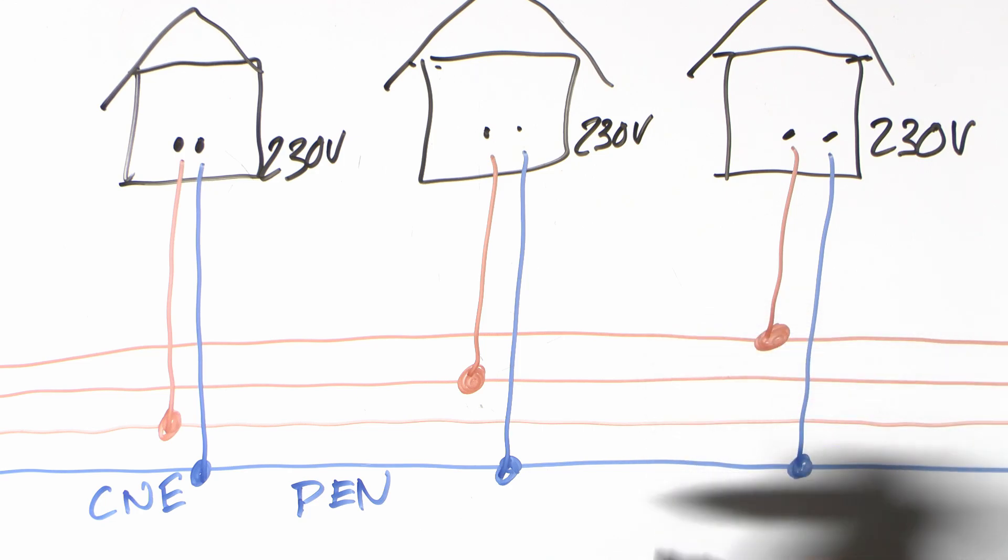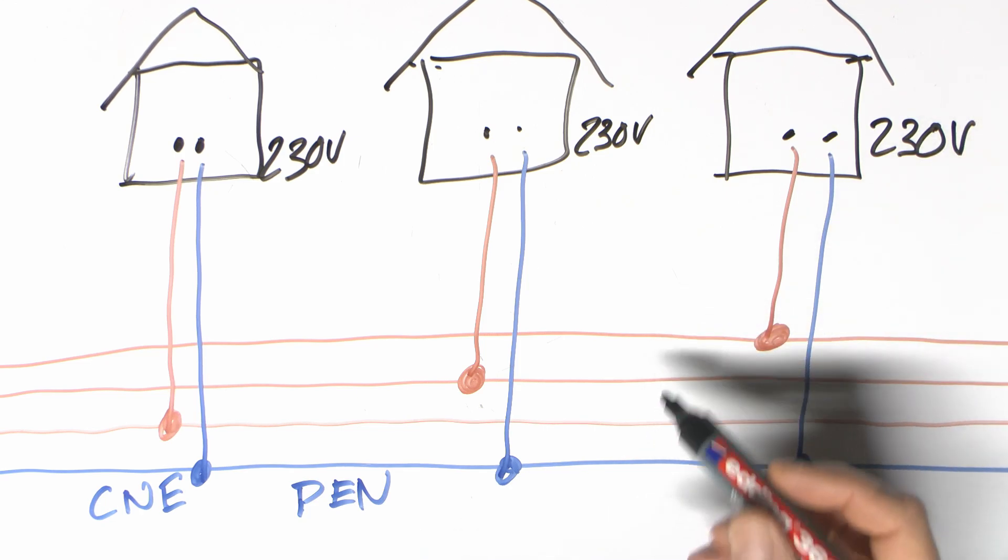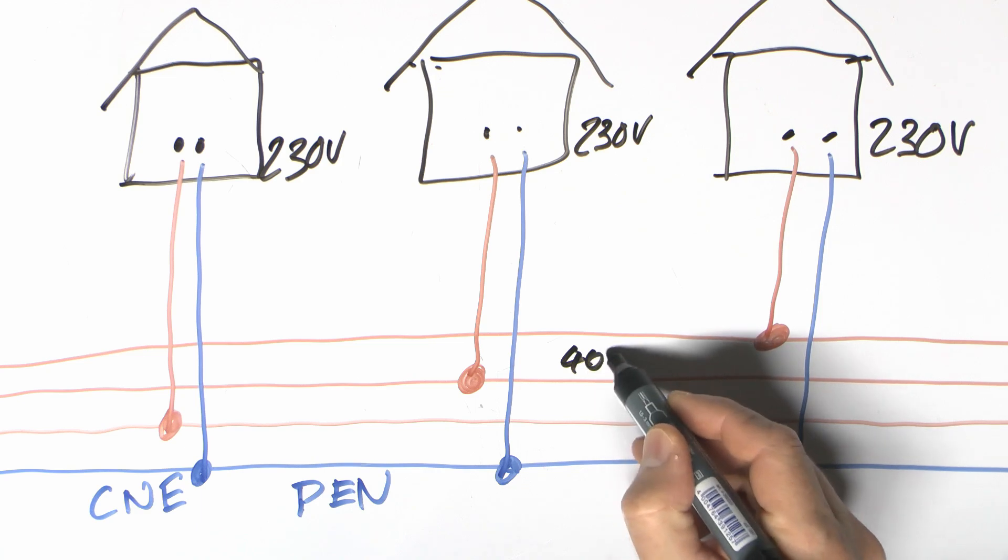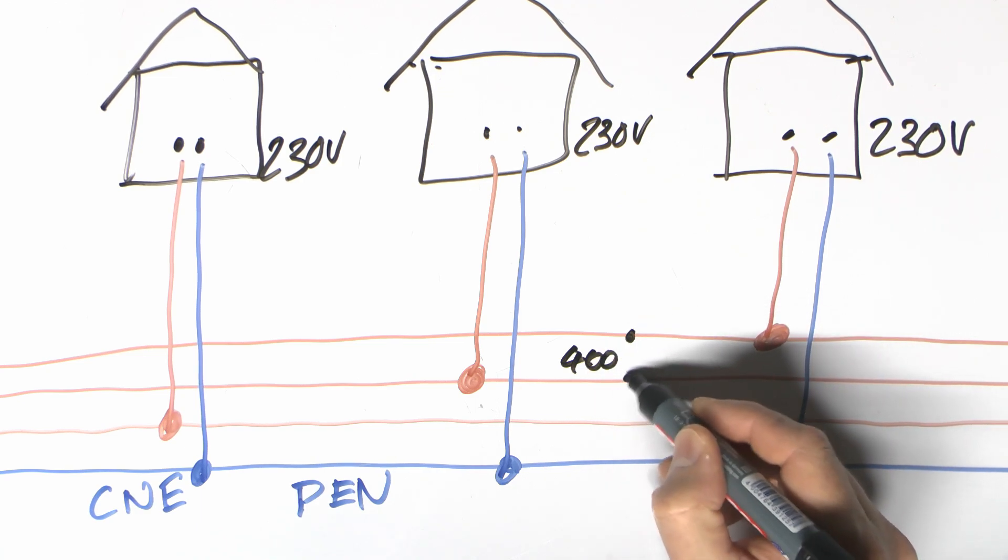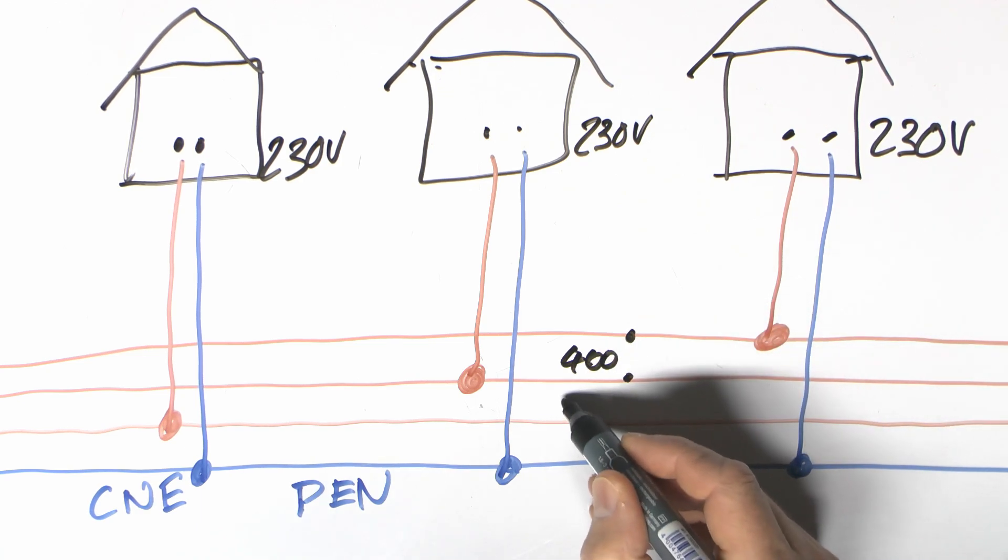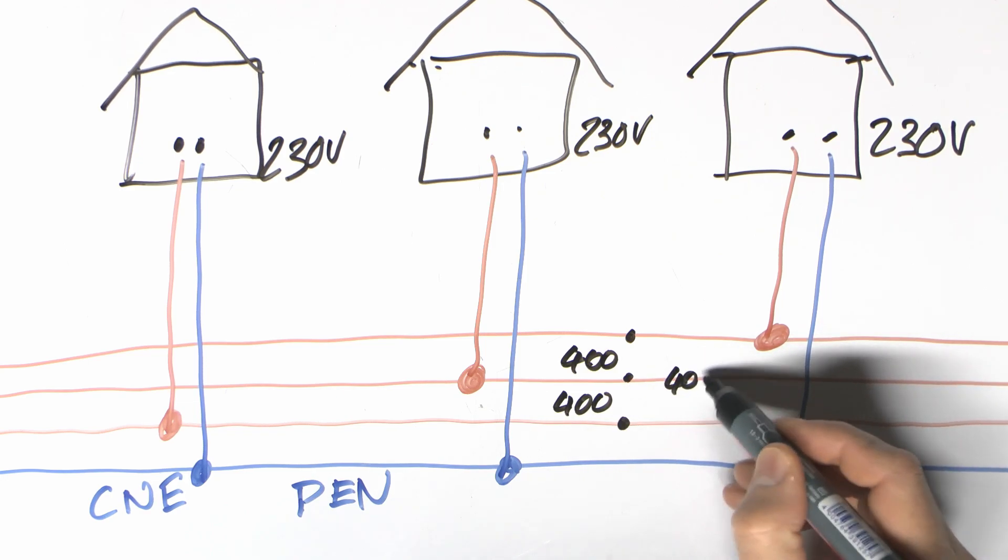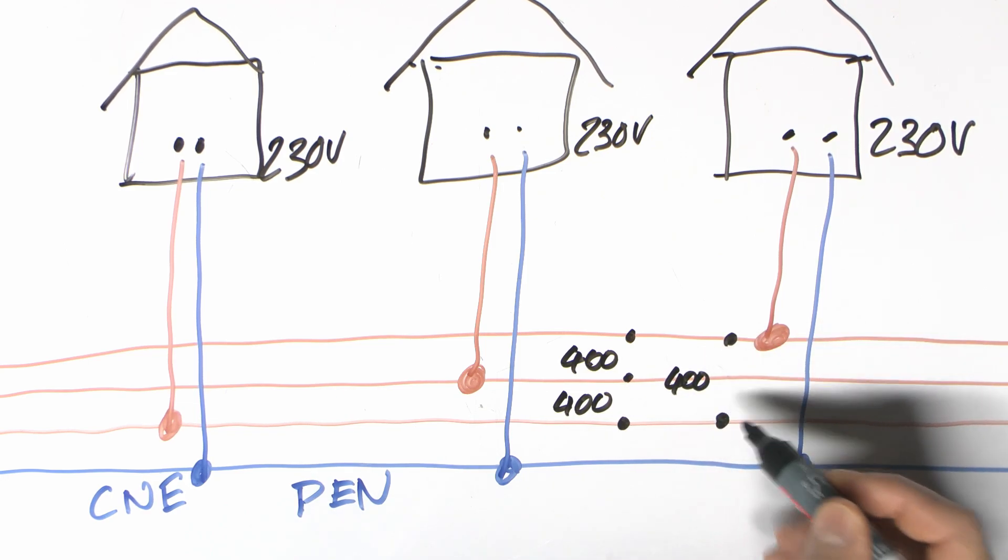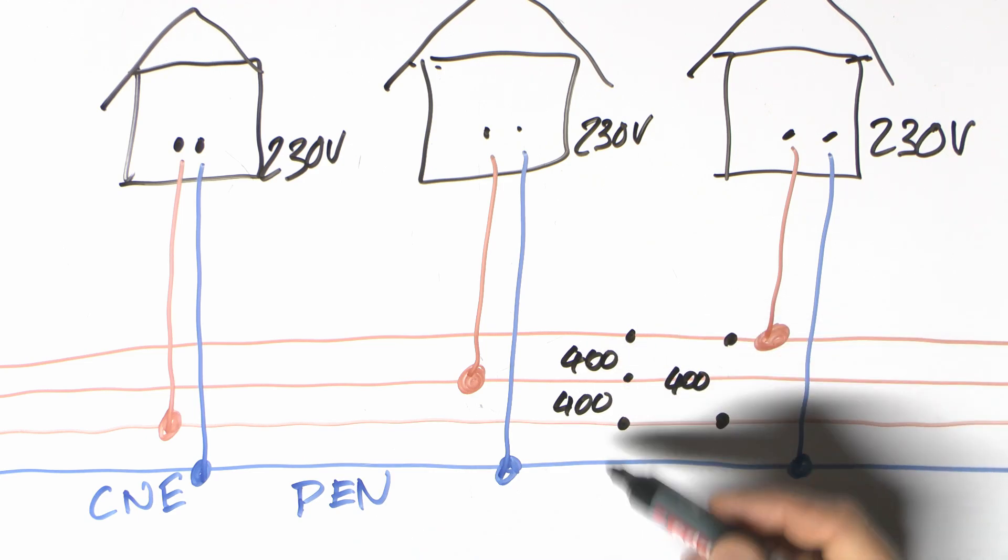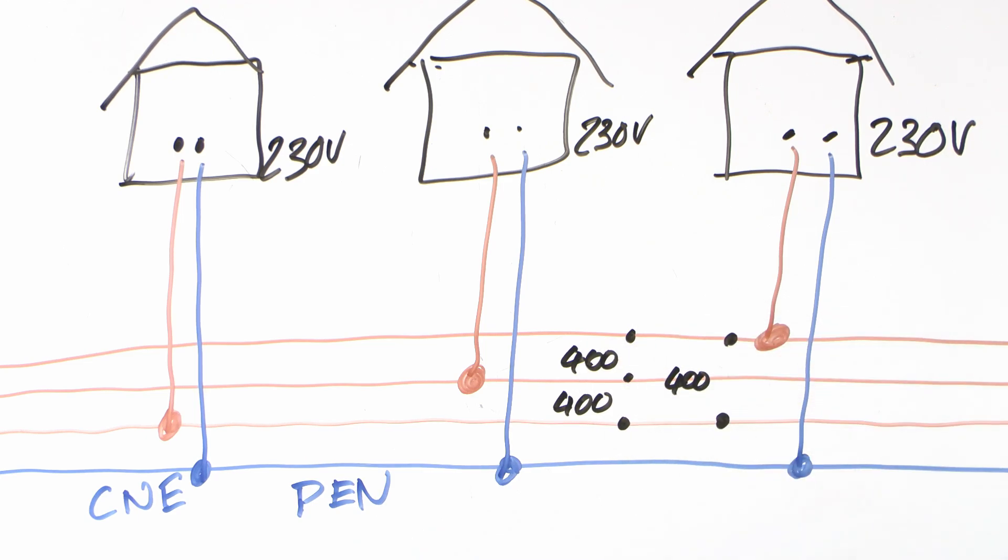They come from the same transformer, but these three are 230 volts relative to the neutral and the earth conductor in this case combined. And that would also be 230 volts relative to the general mass of earth as well. But between each of these is not 230 volts. It's actually 400. So you've got 400 between those two. You've also got 400 between those two like that. And you've also got 400 between the other two. So any two of those, it's 400 volts between all of them.